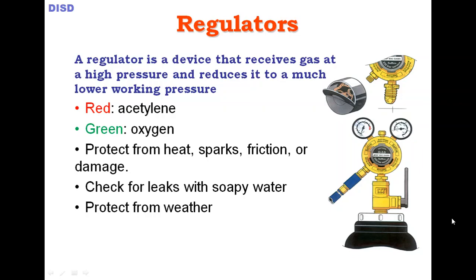When checking the regulator, first check the nature of the cylinder and the gases. To check for leaks, apply soapy water to the connections after attaching the regulator. If a bubble forms, there is a leakage. If there are no bubbles, your regulator is good and working fine.